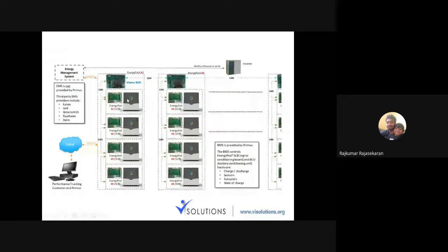Internally they have the signal conditioning unit, as well as the signal which will be acquired from the battery. It will be converted to something your CompactRIO can read, and once it is read, it will be processed inside the CompactRIO itself. The CompactRIO will transmit data from this battery to other batteries using something called a controller area network, that is CAN. Normally CAN is used in automotive systems, but you don't have to use it only in CompactRIO systems. So there are 4 individual batteries, monitored by individual battery management systems.